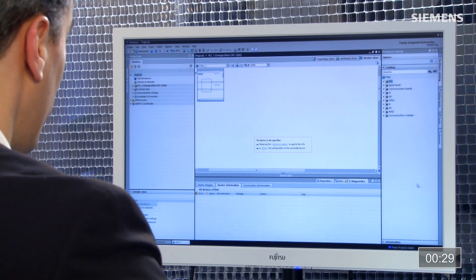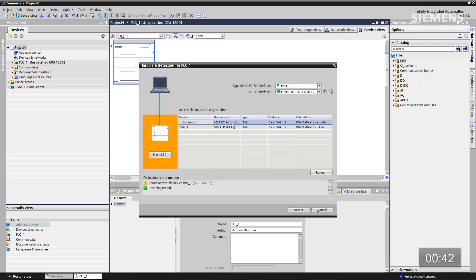The next thing you see is we have a little pop-up box. If I click the Detect button, I'm going to go out and scan the PROFINET network real quick to find that IP address and bring it into this pop-up box. Now that I see the correct IP address for the CPU, click Detect again. This time we'll scan the network and find the correct part numbers for the CPU, the signal modules, including even the communication modules — of which we have a GPRS module for this particular project. So what we physically have now is the actual correct hardware. We didn't have to use the catalog whatsoever to pick and choose all the piece parts. We're ready to actually change an attribute and move on.